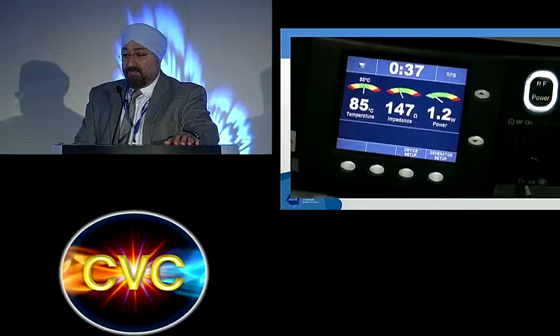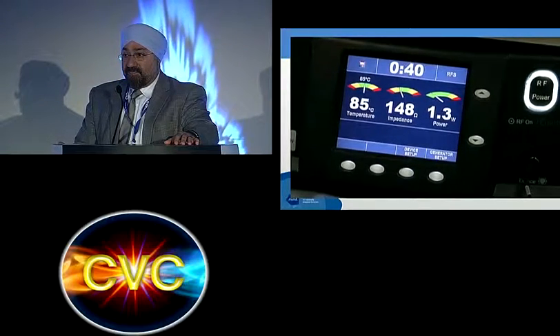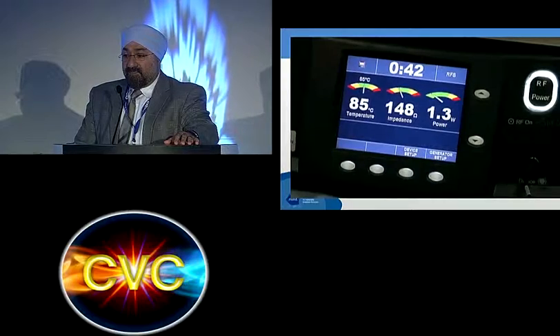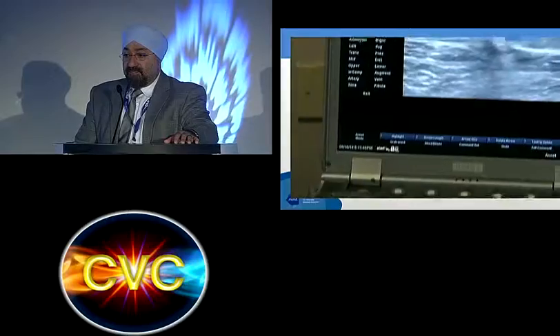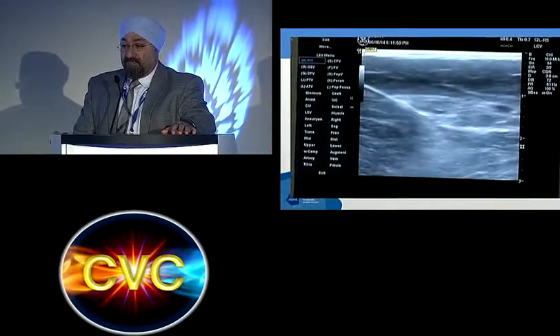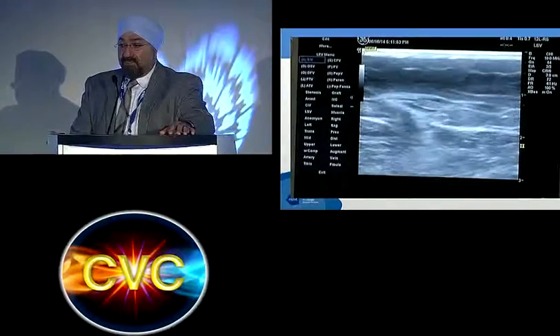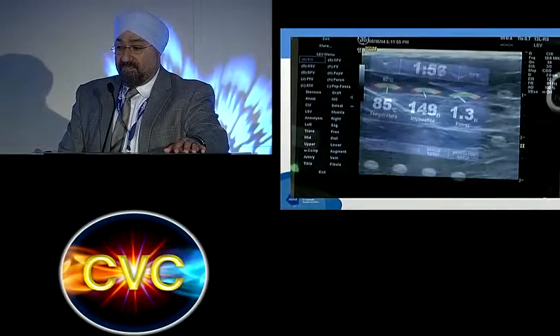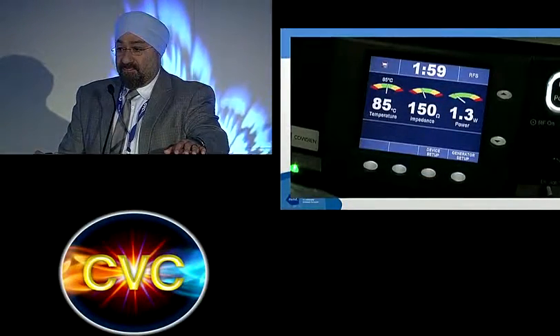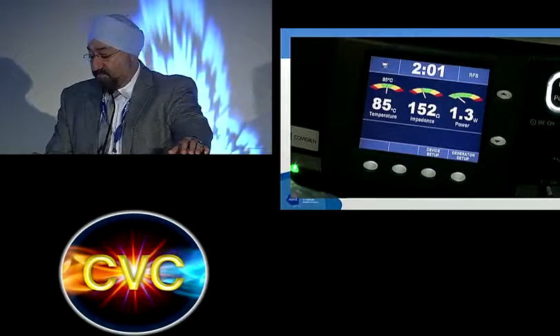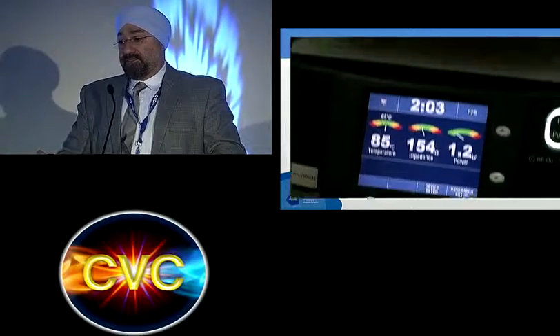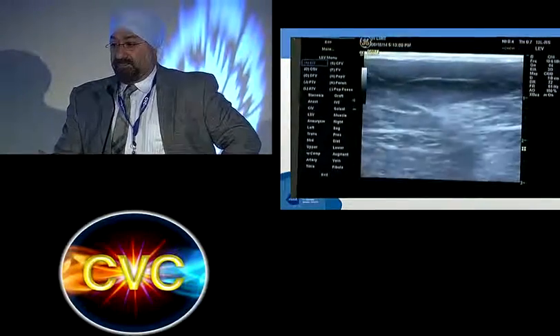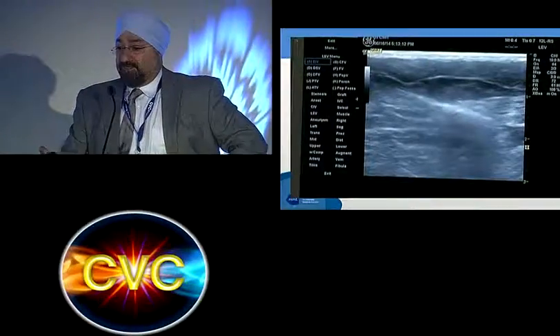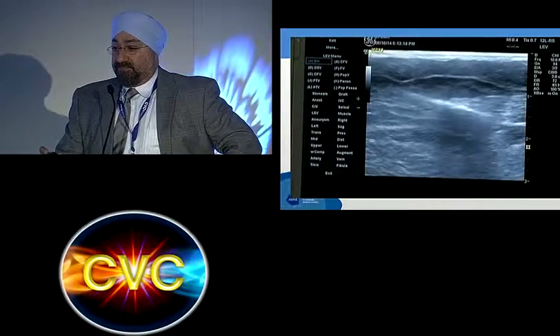So you'll see as the seconds go on, the impedance has stayed in that range. And we'll go back and look at the ultrasound screen, and you can see the location where the heat is being applied, and it's right in the spot where I want it to be. So you can see we're now at just about 2 minutes, and if you go up to the ultrasound monitor, we'll see we're in the same spot and that is still continuing to apply the heat, but you can see the coagulum around it and the echogenicity.